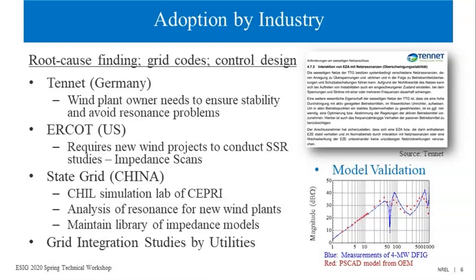What you see on the bottom right side is a plot comparing the impedance response that we measured at NREL for a 4 megawatt wind turbine and a PSCAD model from the OEM. So impedance response can also serve as a very good tool for high fidelity model validation. Sometimes if we do validation just through a dynamic or transient event like a fault, it may not capture all the rich dynamics at different frequencies, but this way we can validate the model over a broad frequency range.